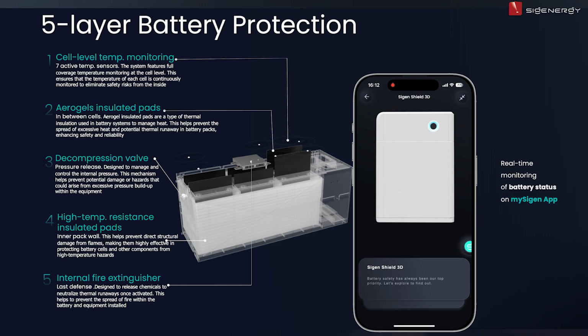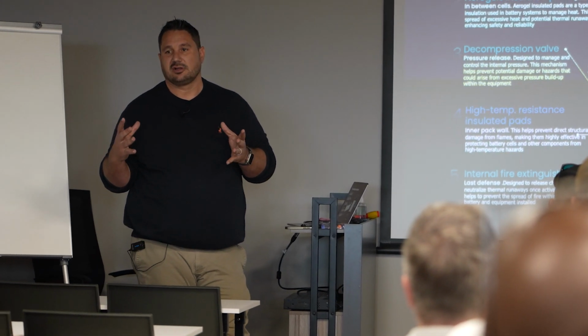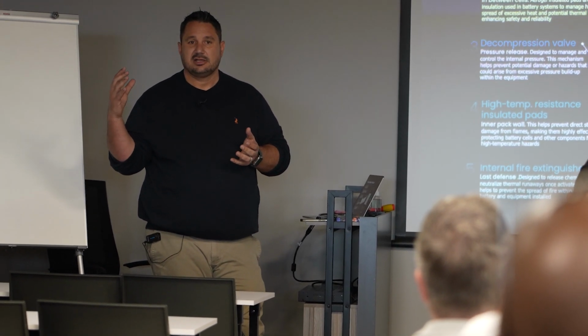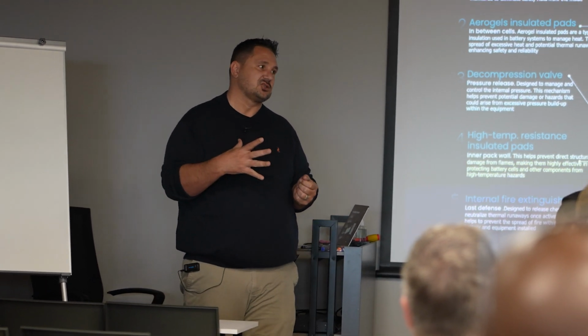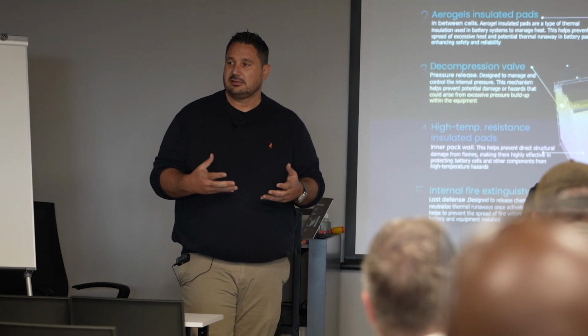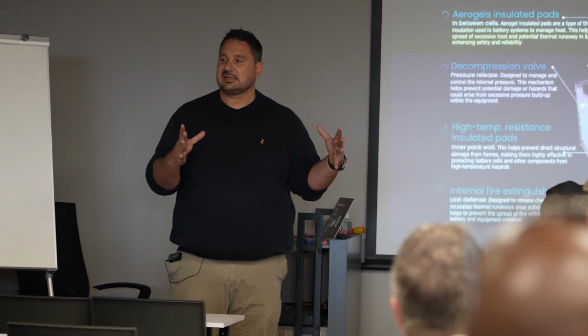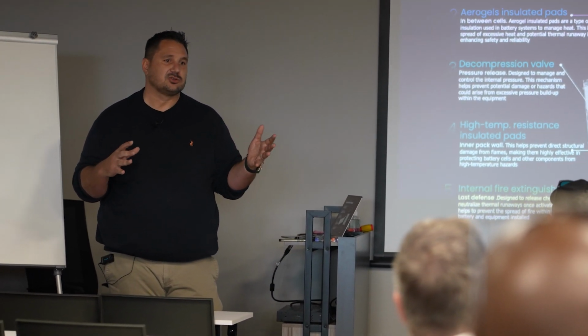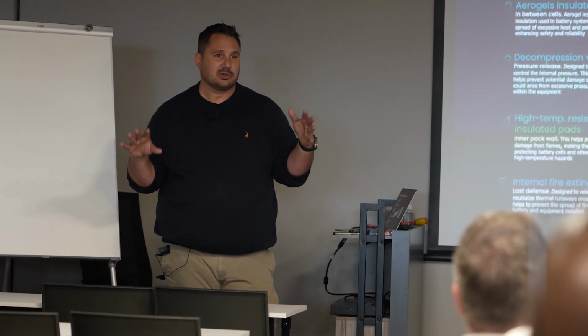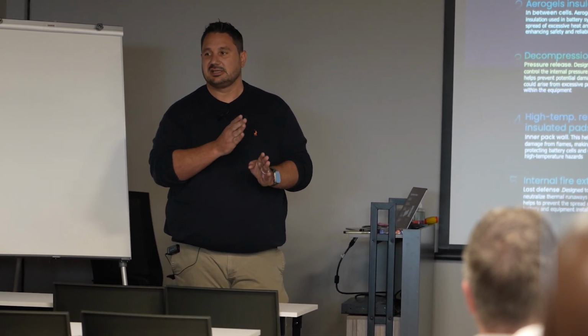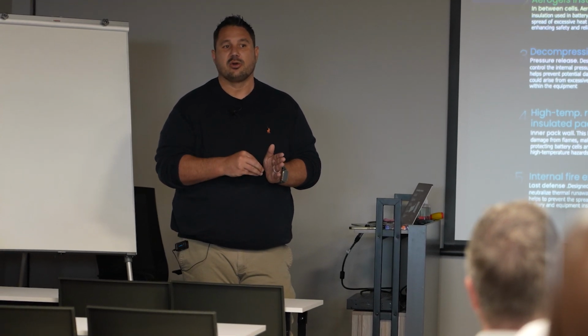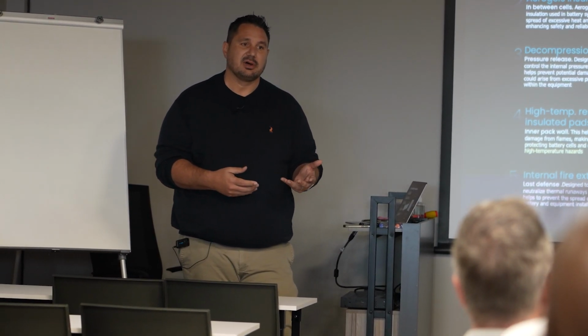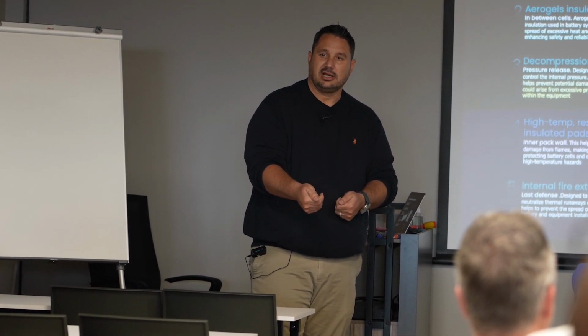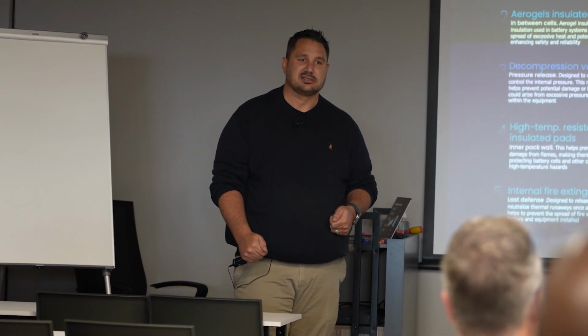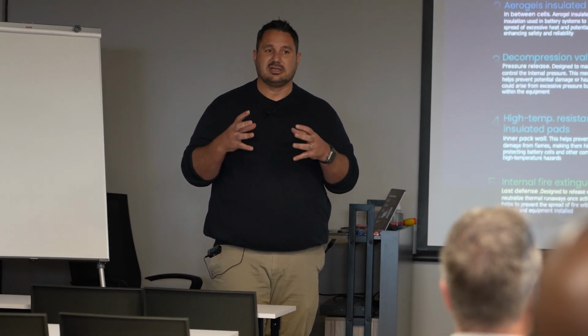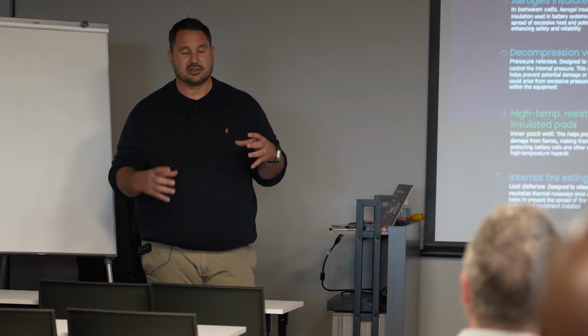If you take container builds, we use the same kinds of aerosol gases inside the containers. If there's a fire, the aerosol gas gets dispersed, kills the fire, and then stays inside the container for roughly 20 to 30 minutes before it dissipates - long enough that there's no reignition. One thing about lithium is you can hit it with a fire extinguisher, wait about 5 minutes, and it starts flaming up again, so this gas makes sure there's no reignition.